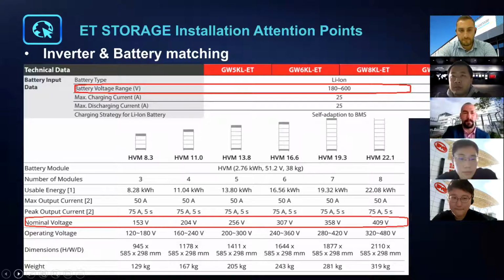When we usually talk about storage, especially low voltage, the key thing for us is to decide the proper battery size. Just make sure the battery is not too big or too small for the customer. But with high voltage storage, besides the battery size, there's another key part: we need to make sure the voltage coming out of the batteries can actually stay within the inverter's required voltage range. So basically, it's very similar to the MPP range on the string inverter.